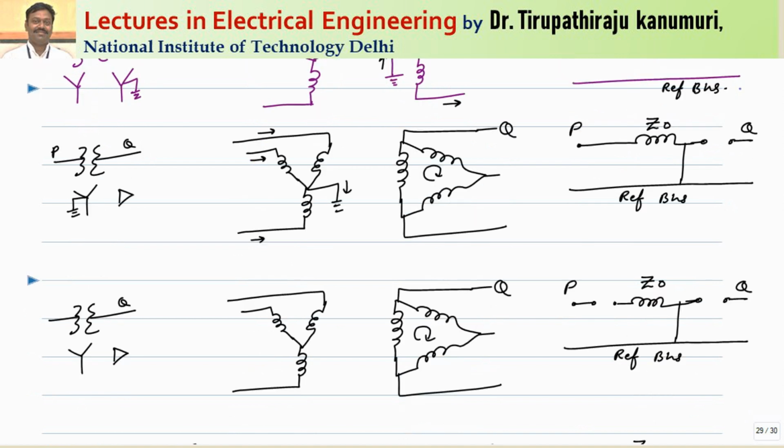So let us take the case of primary side is star connected with neutral grounded and secondary side is delta connected. So now if the secondary side is delta connected, let us assume the fault happened somewhere, but this delta cannot supply the fault, but it can circulate the currents within this only if the zero sequence components are induced. So that's why in the secondary side you can see the series switch I am representing with open switch, because the impedance offered for zero sequence in line is infinite, because we can take it as equivalent to Zn is not connected, that's why it is open circuit. Whereas as it can circulate within this loop, that's why I am closing my shunt switch in the secondary side.